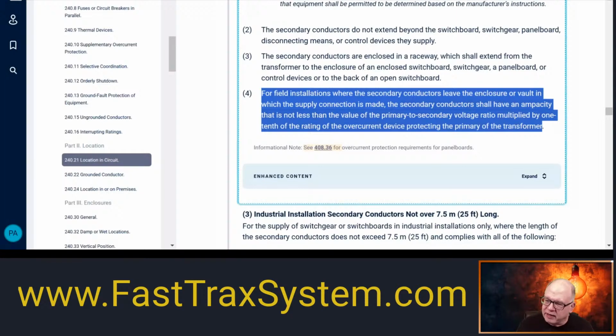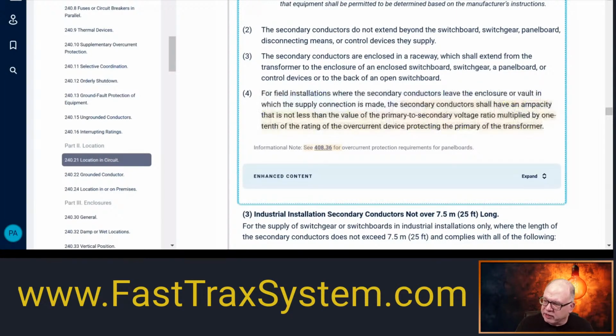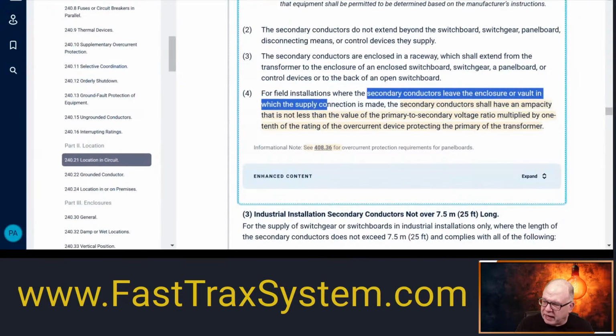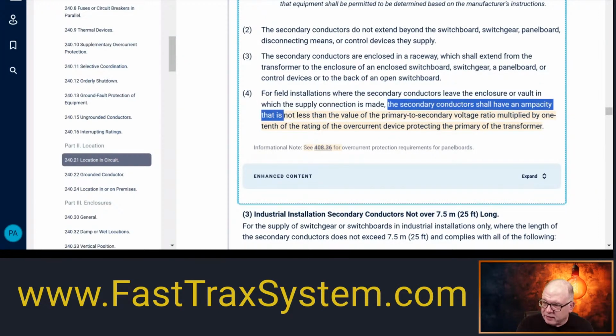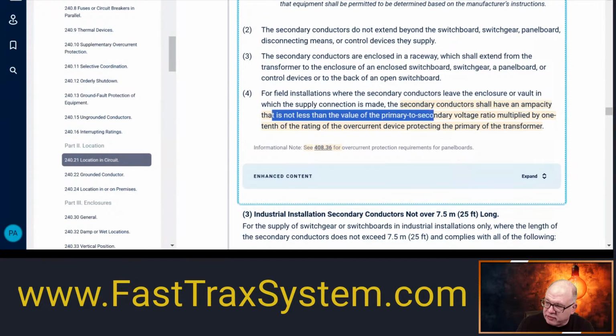All right, and it says, for field installations where the secondary conductors leave the enclosure or vault in which the supply connection is made. So it's saying leaving the wireway and going to your equipment. In this case, it's also leaving the transformer enclosure and going to your panel. Same concept. It says the secondary conductors shall have an ampacity, so this is a minimum, not less than the value of the primary to secondary voltage ratio.